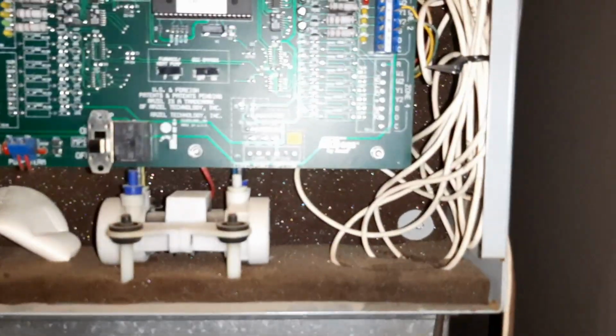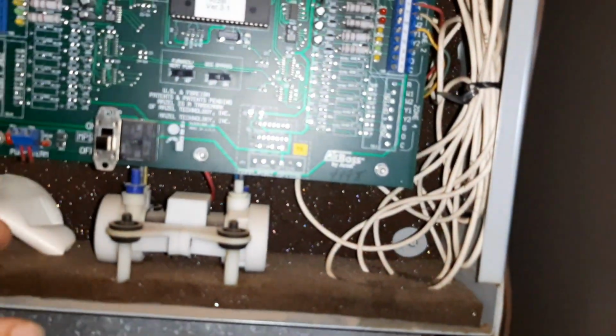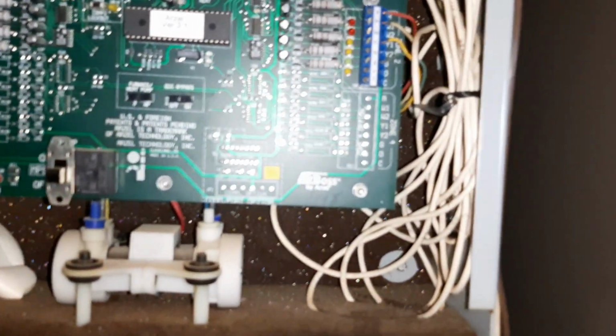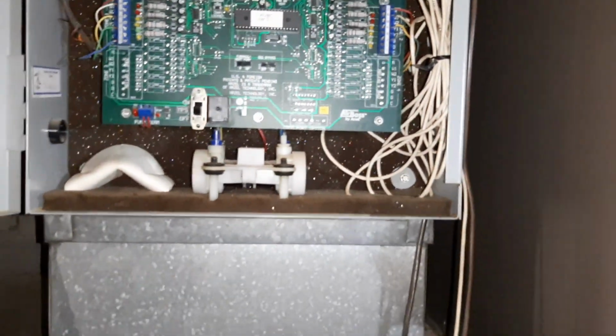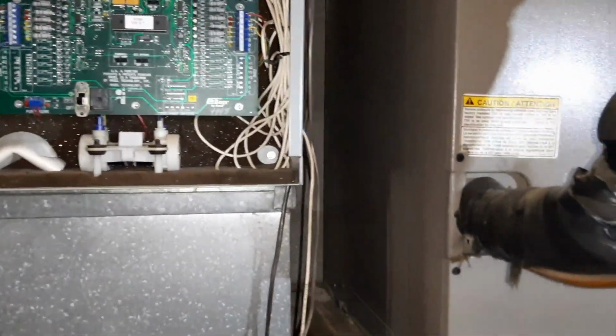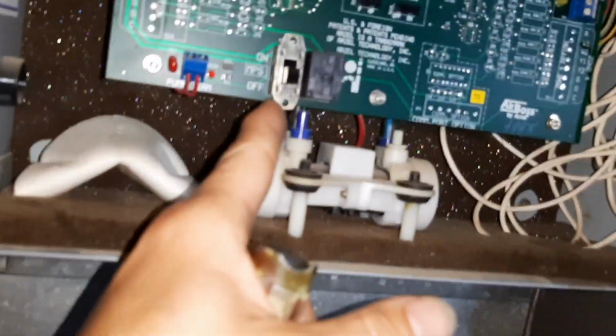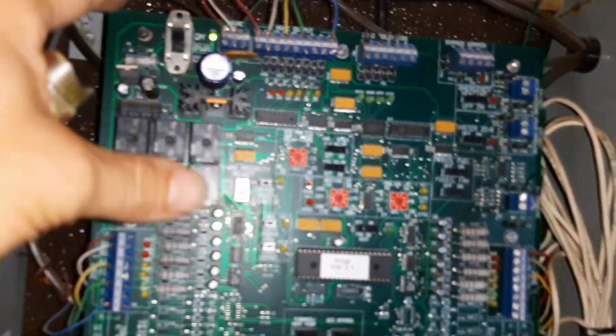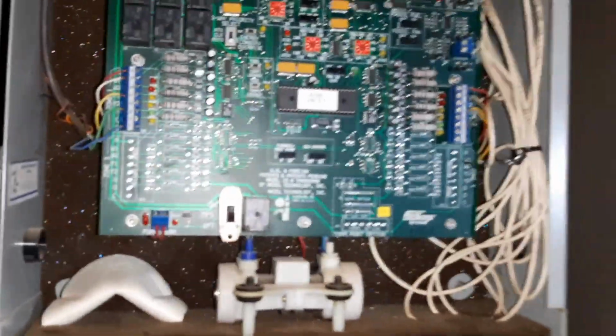The complaint was that this one wasn't cooling upstairs, so we might have a problem with the zone controller. I'm going to have to verify that those dampers are open somehow. I haven't dealt with too many of these, I've seen them before, but I might have to dig into it. As long as my dampers are open, this is turned off. An MPS, I don't know what that is. Power is on, so I'll have to see if it's giving me any outputs or what it's doing.